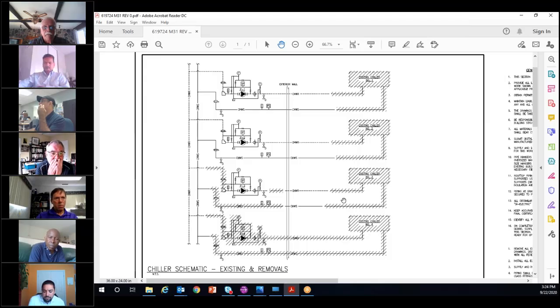So there were a few things from a design standpoint that we had to consider here. First off, the original system that you can see here was 4 individual air-cooled chillers, each with their own dedicated pump, all operating on chilled water. The hospital was operating on a very typical 44-54 Fahrenheit chilled water system. All of those 4 chillers then pumping into their main chilled water supply and return that goes to their various cooling loads and air handlers throughout the hospital.